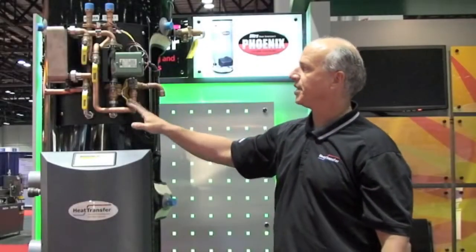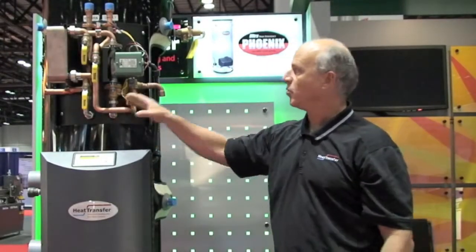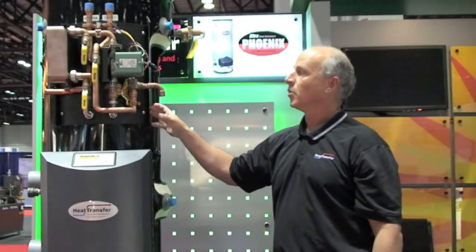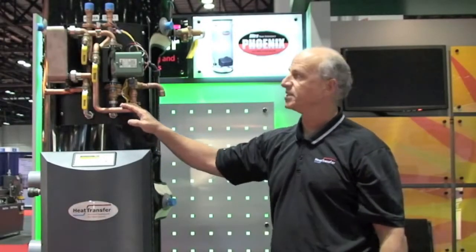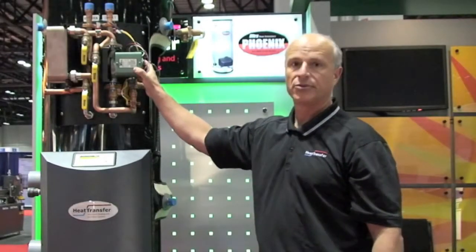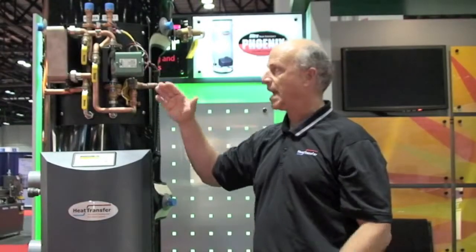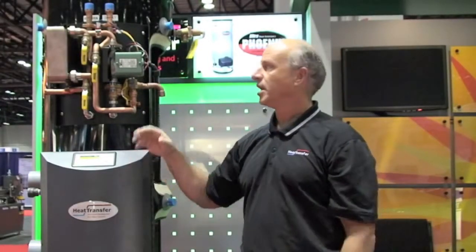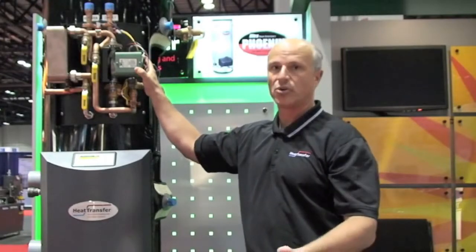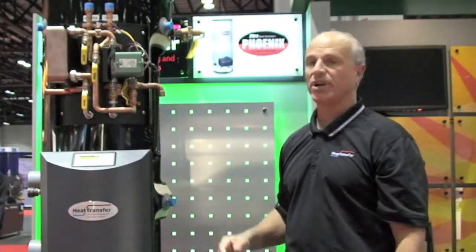The beautiful part about this is it's an integrated system. You have one tank that provides thermal storage, basically gives you hydraulic stabilization, and in one simple package. Another nice feature about the system is that with system loads, we can modulate the pump to achieve actual system load balancing with the central heating in order to accommodate small zones or other things that can create short cycling normally with conventional systems.